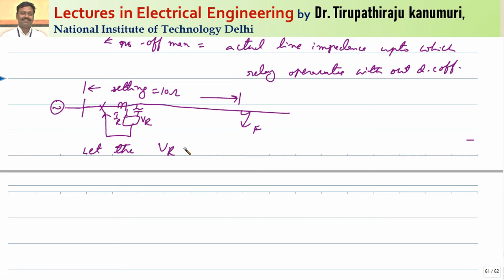Let the voltage at the relay, VR, be 100 volts and the fault current without offset, that is without the DC component or the steady state component which we have analyzed till now, be 10 amperes. Then the impedance that is protected is 100 volts divided by 10 amperes, equal to 10 ohms. So the value of Z set is 10 ohms. It should operate up to 10 ohms, which corresponds to the line length.